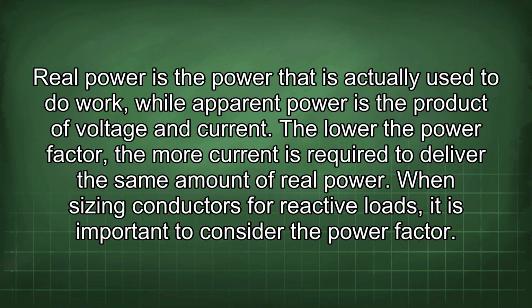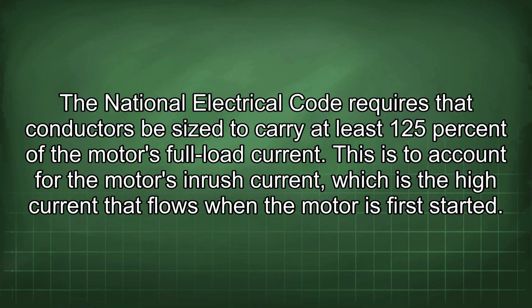Real power is the power that is actually used to do work, while apparent power is the product of voltage and current. The lower the power factor, the more current is required to deliver the same amount of real power. When sizing conductors for reactive loads, it is important to consider the power factor. The National Electrical Code requires that conductors be sized to carry at least 125% of the motor's full load current.